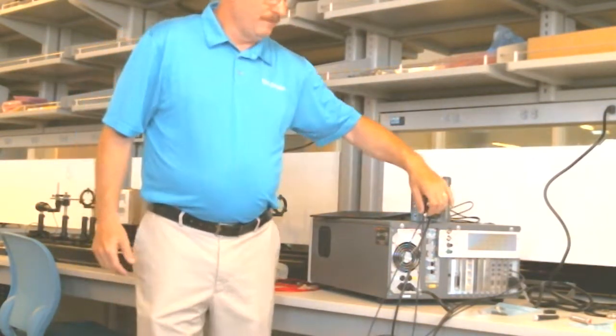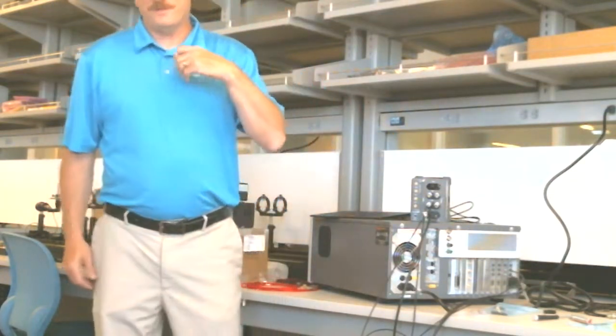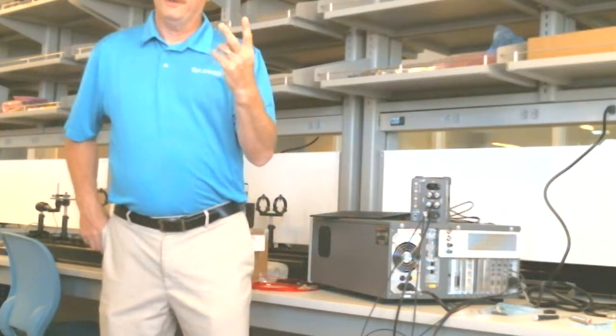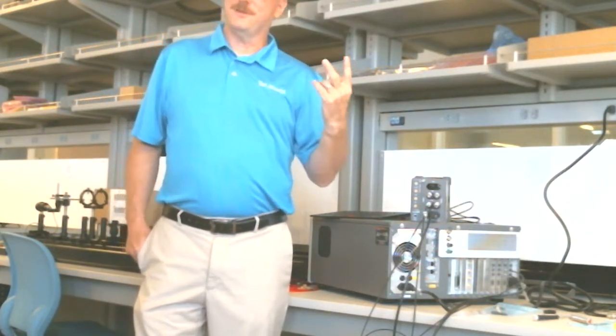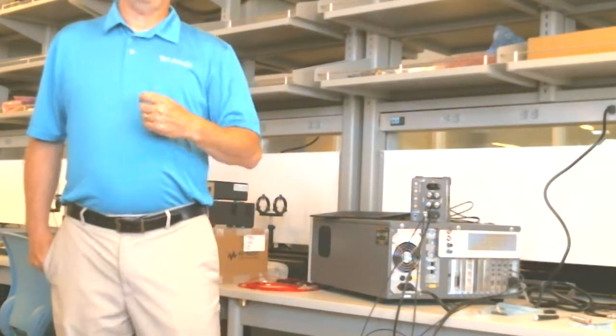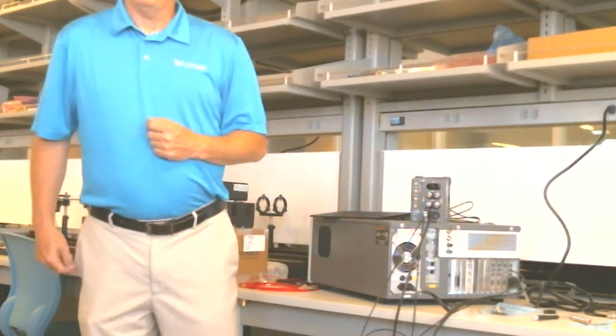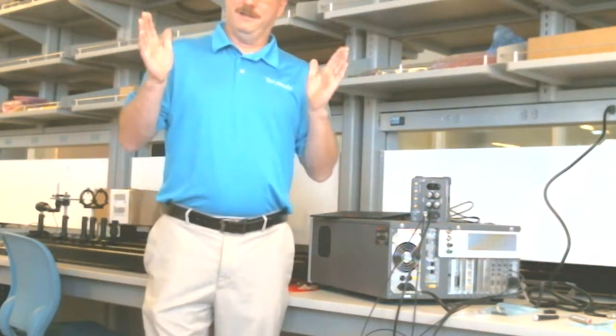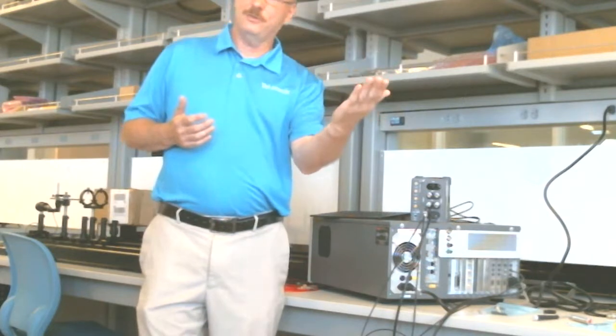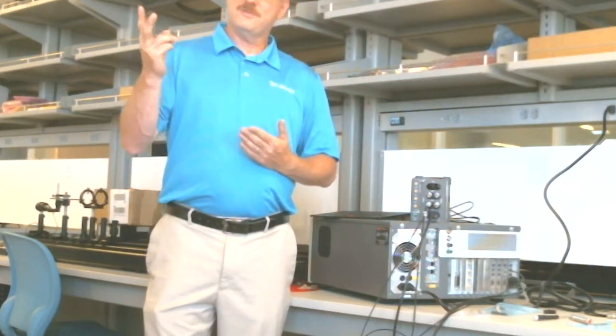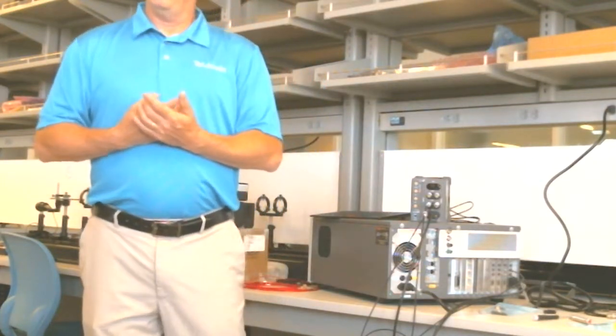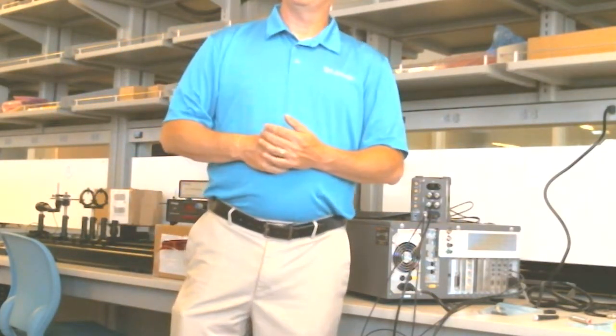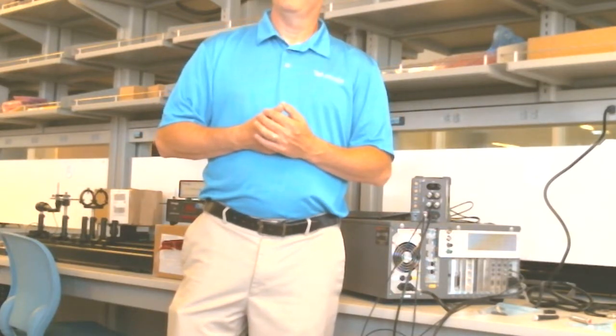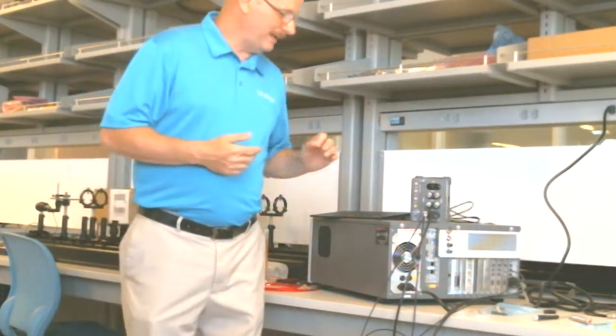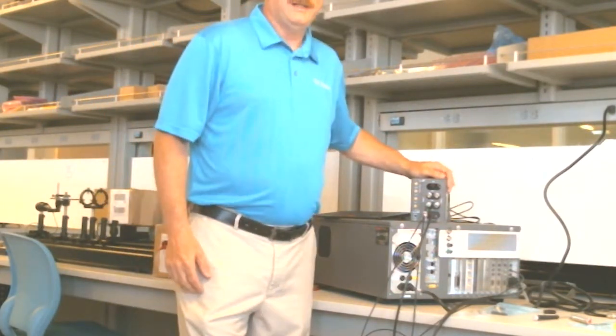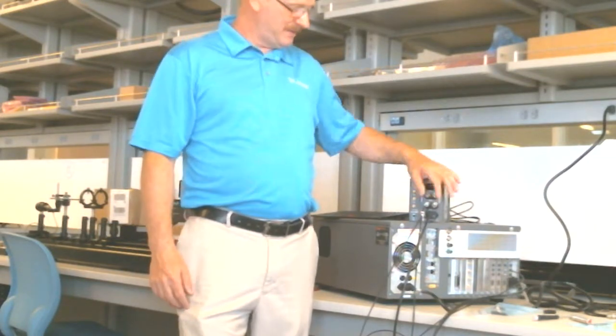Same thing here. This works because if you source and measure on the same pair of wires, you're into a low impedance, so the resistance of those wires matters, there's an IR drop across the cables. But if I separate the force and the sense, I source on one set of wires and sense on a different set. Those sense wires go into a high impedance buffer, so the current through them is zero, and the drop across the cables doesn't matter. So when we say we want to force 2 volts to the device, we get 2 volts, regardless of the resistance of those wires.